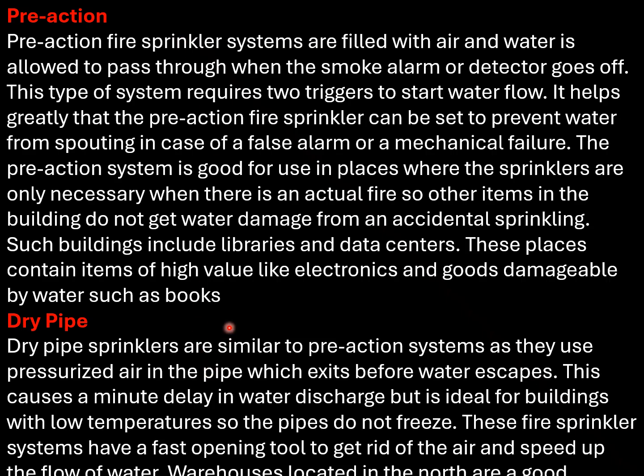Dry pipe system or dry pipe sprinkler system is similar to the pre-action system as they use pressurized air in the pipe, which exits before water escapes. This causes a minute delay in water discharge, which is ideal for buildings with low temperatures so that pipes don't freeze. These fire sprinkler systems have a fast opening tool to get rid of the air and speed up the flow of water. Warehouses located in the north are a good example. North of the globe.